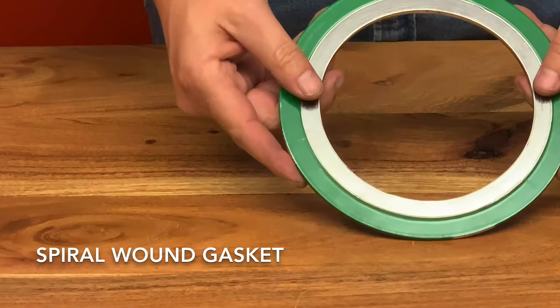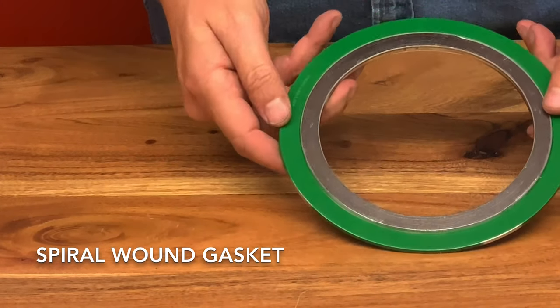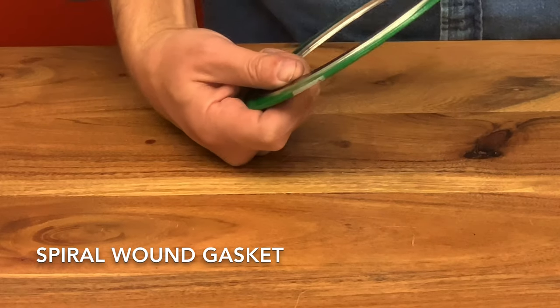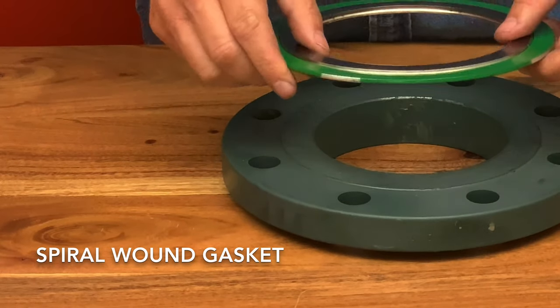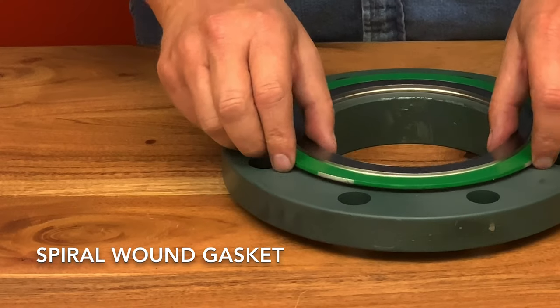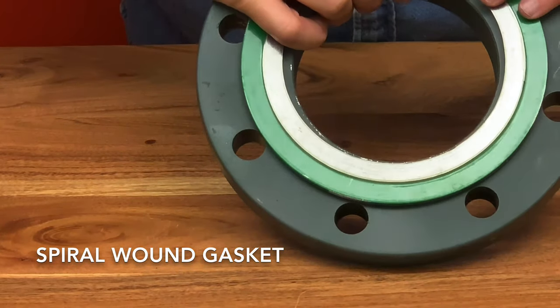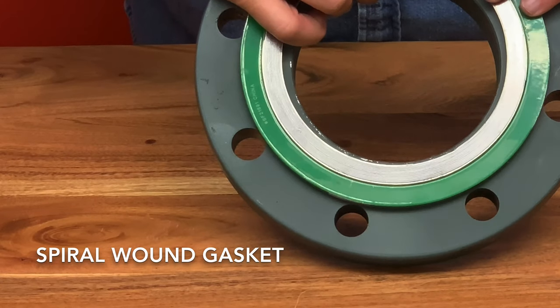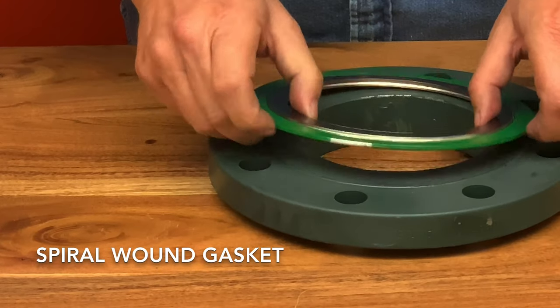The spiral wound gasket with reinforcement rings has the sealing element formed by winding two materials into very thin V-shaped spirals. Different configurations handle different flange designs. This one here is fitted for a raised face flange. The sealing action is actually a result of a combination of the flow of the metal and the soft filler plies when the gasket is compressed.